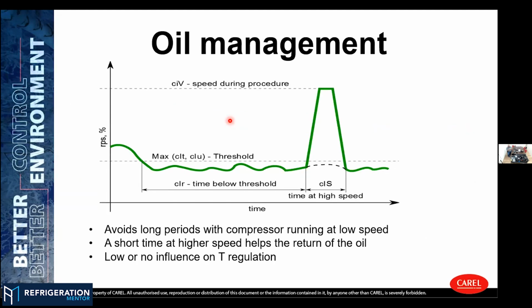And last but not least, I would mention oil management. I talked a lot about the benefits of having a variable speed compressor inside your system. You can modulate, you can save energy, you can have stability on the temperature. But on the other side, the only negative point I can see with a variable speed compressor is that variable speed refrigerant also means variable speed oil dragging back to the compressor. So you need to take care of that.